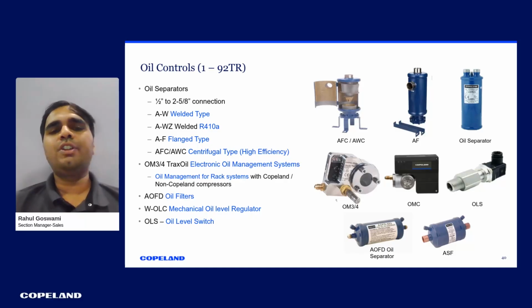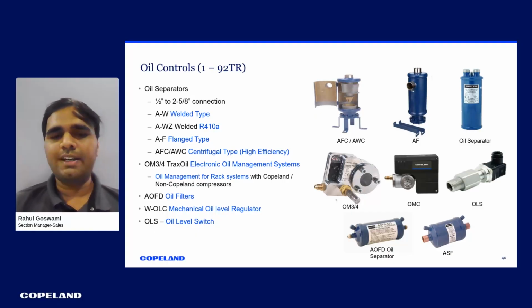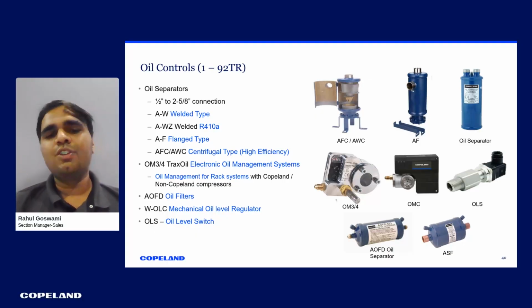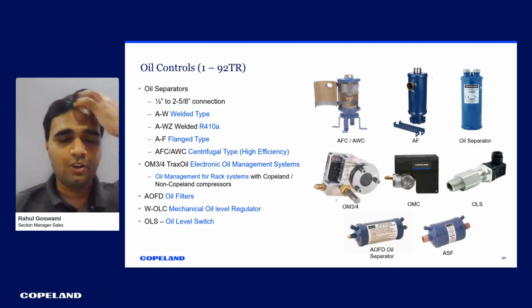So coming down to oil control, it is a very vital part of the refrigeration system as well, so that your compressor doesn't fail, and it ensures that the oil coming out of the compressors goes back to the compressor on time. So we have oil separators. In oil separators, we have 1/2 inch to 2-5/8 inch connections.